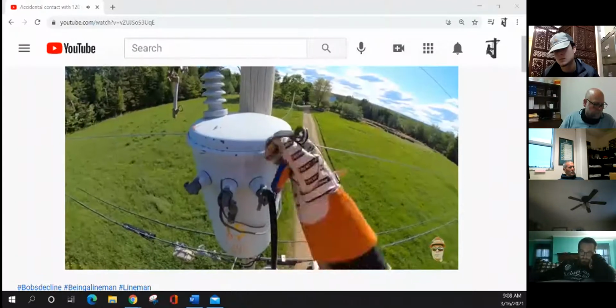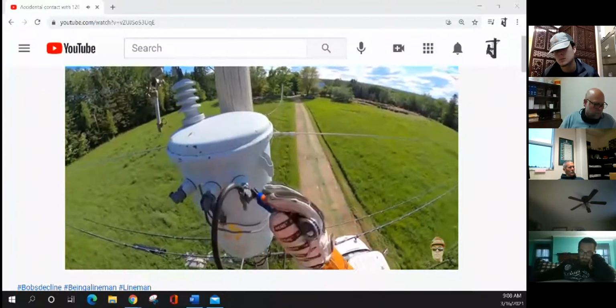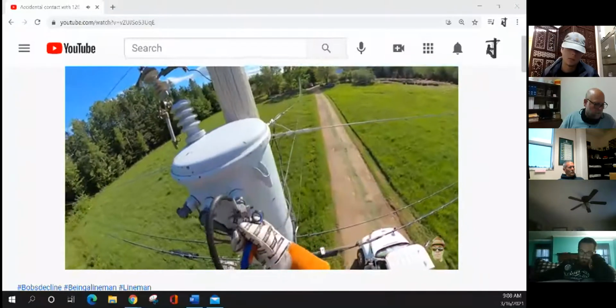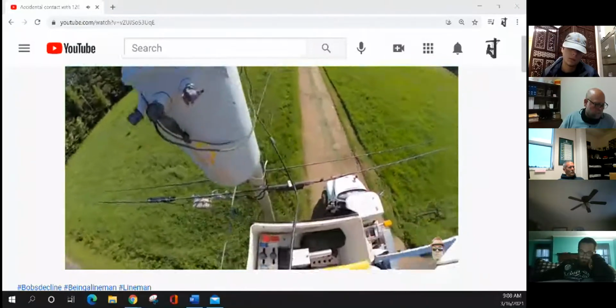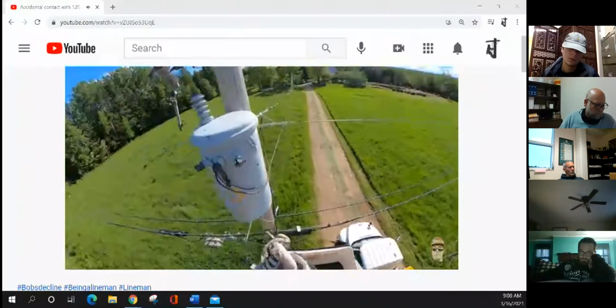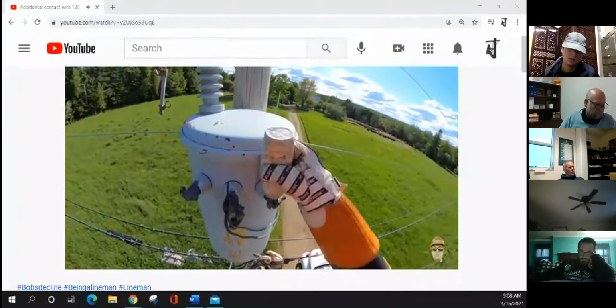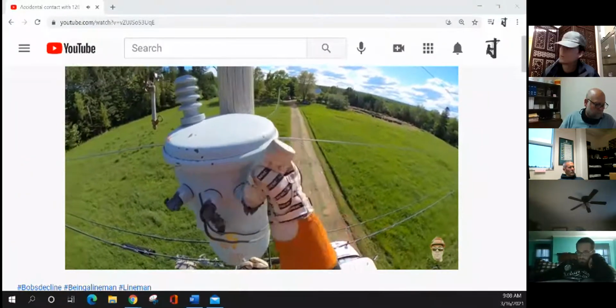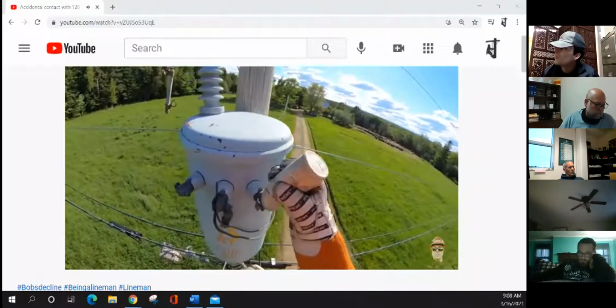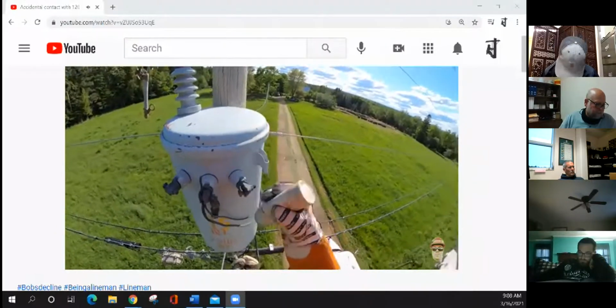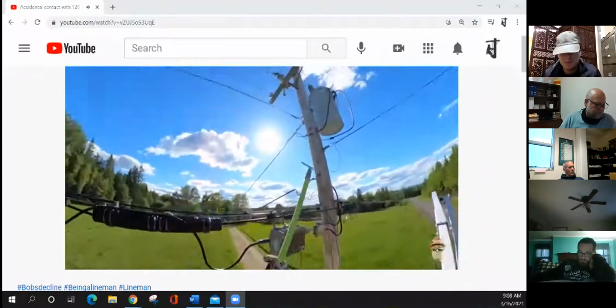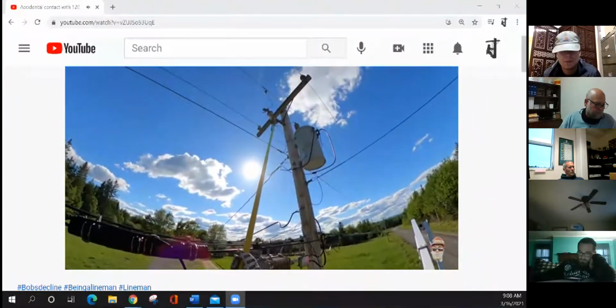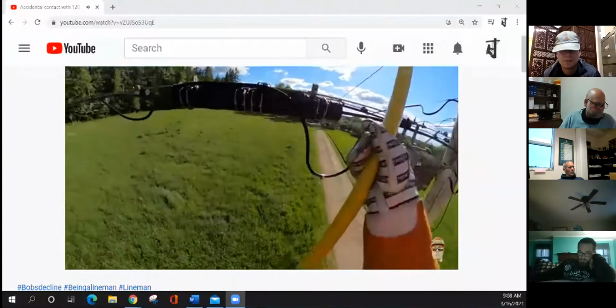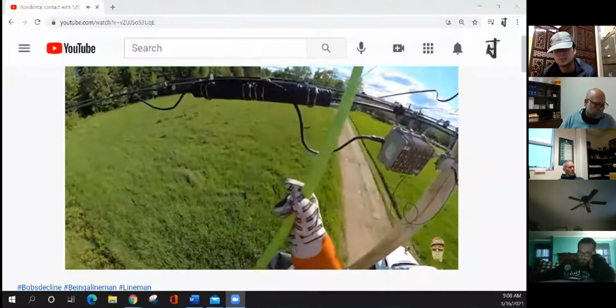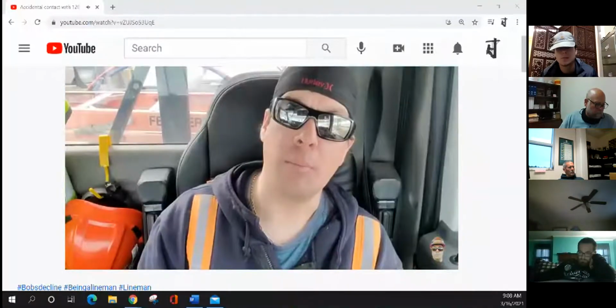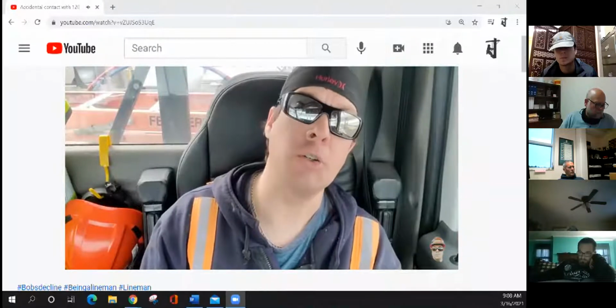The line coming out of the transformer to your home, that 120 volts, doesn't sound like much. It's not fused. If there's a dead short, you've got to rely on the fuse on the primary side in that cutout to blow, and it takes quite a beating before it'll actually blow. So if you make contact with your body on the secondary side between a phase and a neutral, that's not going to draw anywhere near enough amperage to blow that fuse, but there is going to be enough amperage that can cause serious injury.